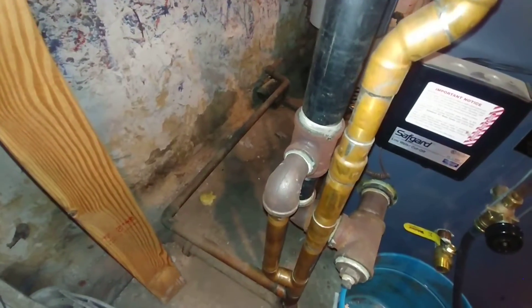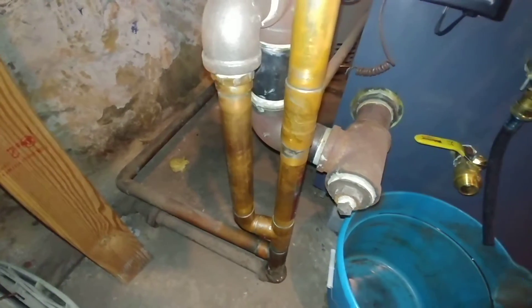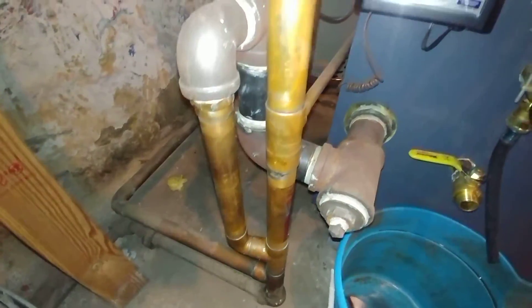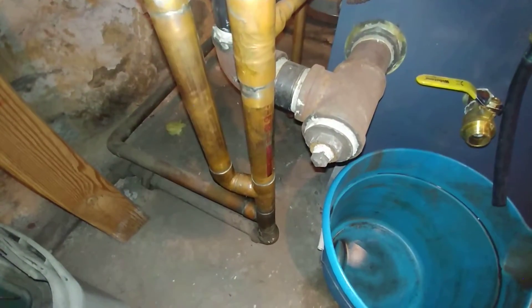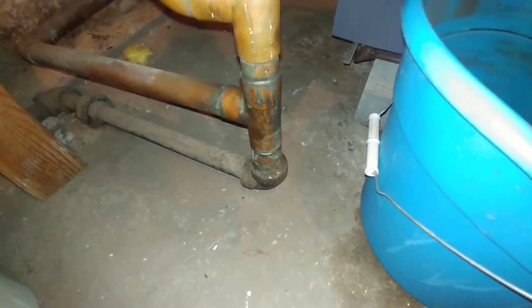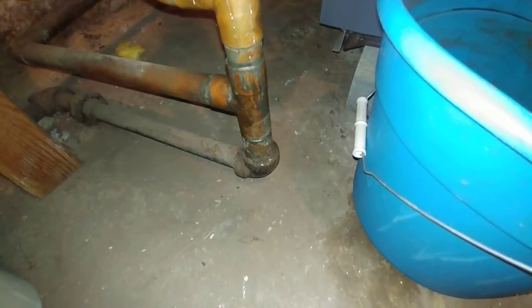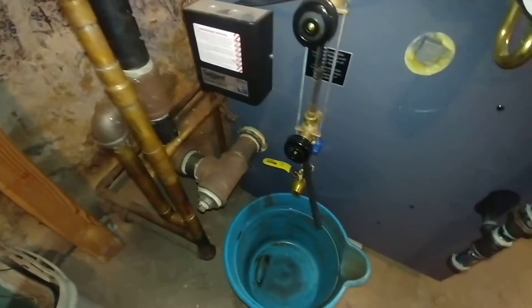I would have liked to have seen stainless steel on that Hartford loop to make a proper transition from the copper to the steel. I would have also liked them to have installed a drain — that would have been extra work, but it could have been done so you can at least drain this wet return, as they get pretty crusty.